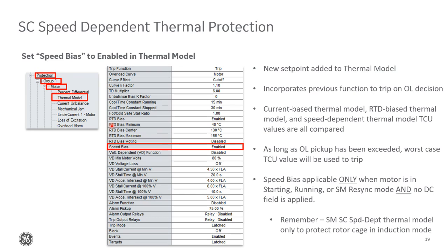So if we see an unusually hot RTD because of something like a high ambient temperature, we'll operate on that quicker. And similarly, if we see an estimate that the squirrel cage winding has reached its thermal limit, we'll trip based on that first. Since this speed-based thermal model is only active during starting, induction running mode or resync mode, this doesn't affect the normal running mode thermal model operation. But if you're already using the speed-based thermal model protection anyway, it doesn't hurt to enable this option here. It's just a little bit of added protection.